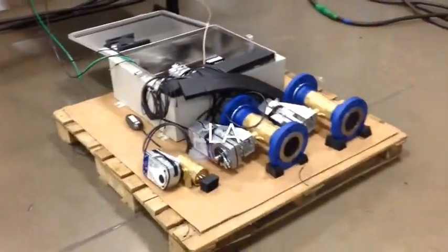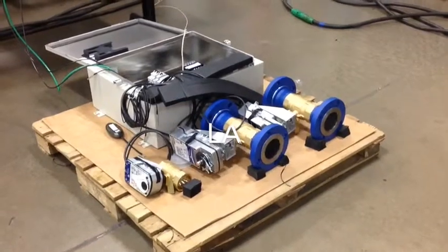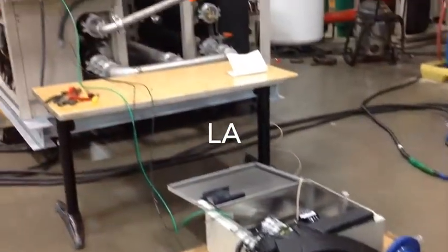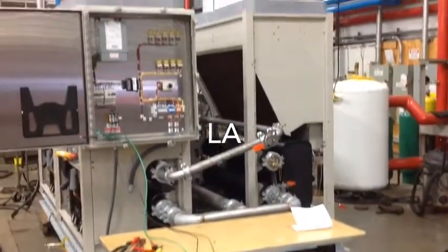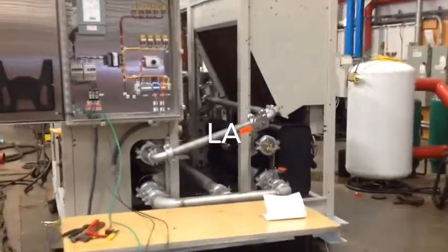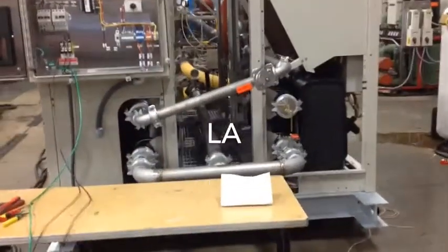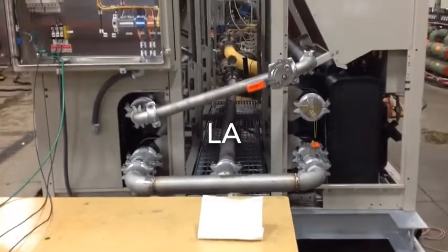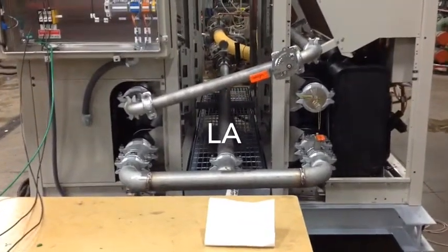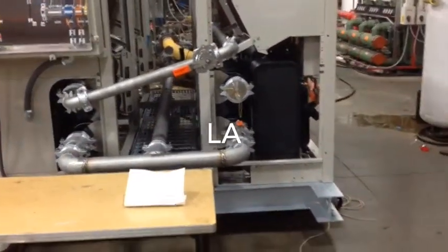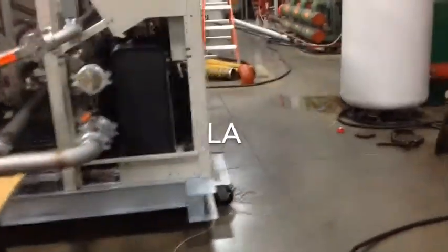This is the heat exchanger control box that will ship loose for mounting by Thermal Dynamics. We confirmed the power requirement to be 220 volt, 50 cycle, single phase with Mike Papke on the phone earlier. You also saw the 3 control valves, the 2 larger valves for isolation and the smaller valve is the bypass line. In the middle there you see the piping heading back through the walkway, that's the leaving connection.